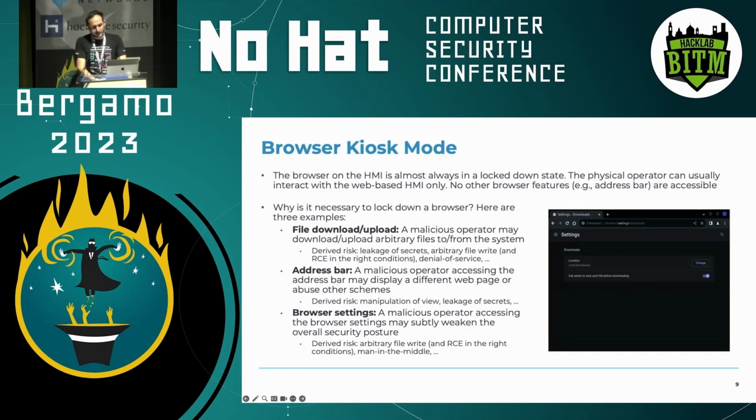On a browser-based HMI, the browser is almost always in a lockdown state. So the operator can interact with the web HMI, but cannot do much more than that. We use browsers every day on our personal devices, and very rarely do we associate the installation or the presence of a browser strictly with a risk. However, this impact and this threat model radically change when this browser is installed in a server system, and when the server system, let me use this term, is used by heterogeneous operators, and when, of course, the server system controls an industrial process.